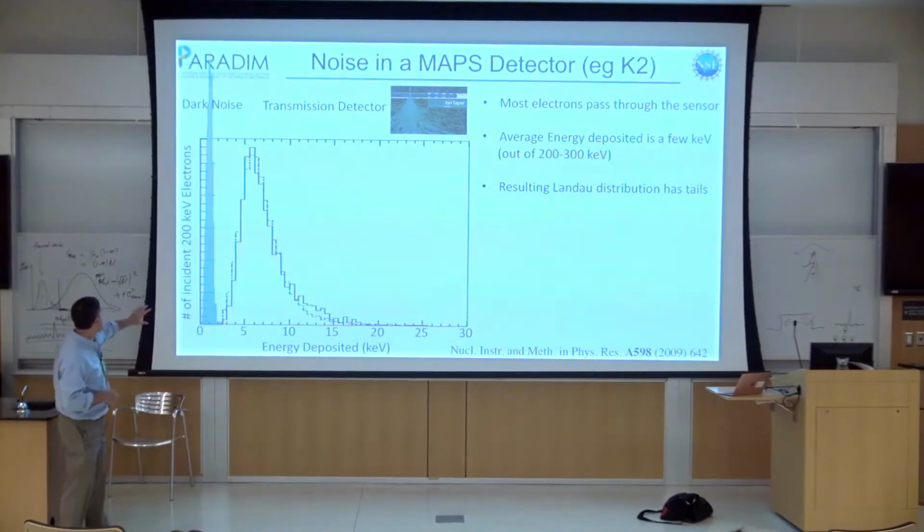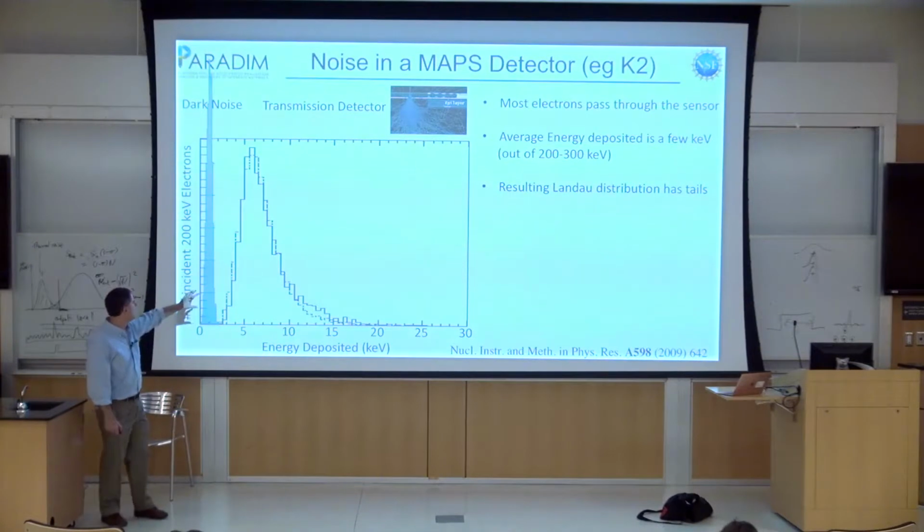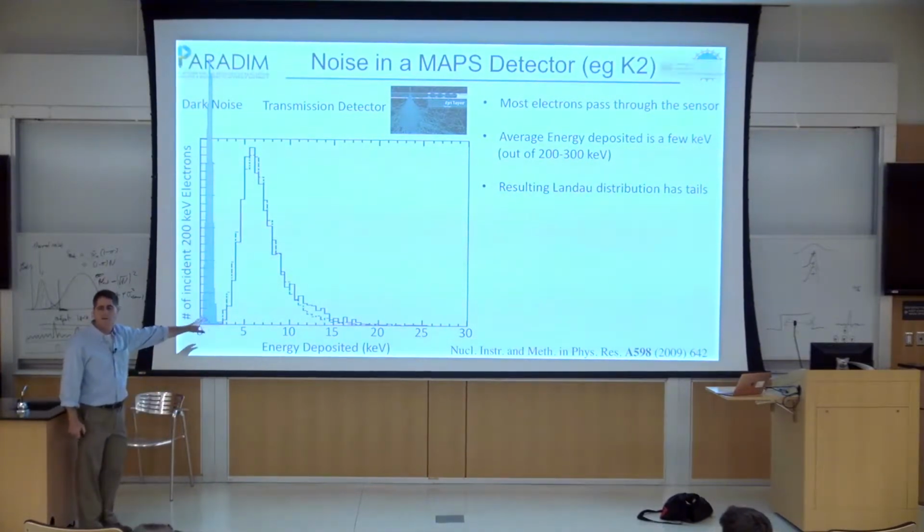So this detector was designed for biological imaging. It wasn't designed for diffraction. It does a great job for biological imaging, but if I've got an image that's very, very sparse, this little overlap tail is still going to cause me a problem.